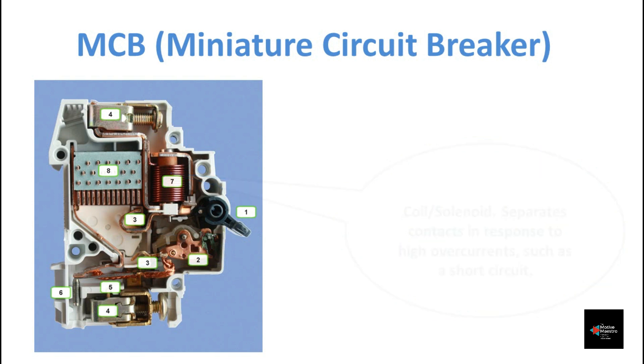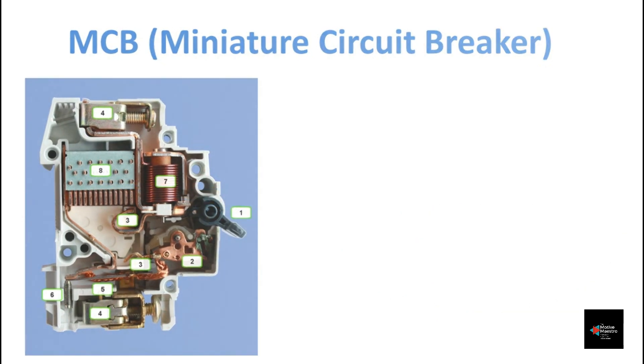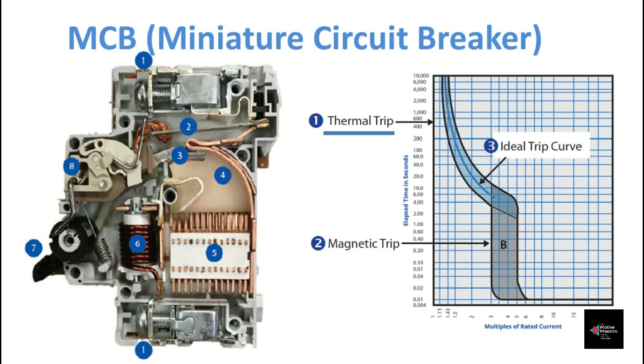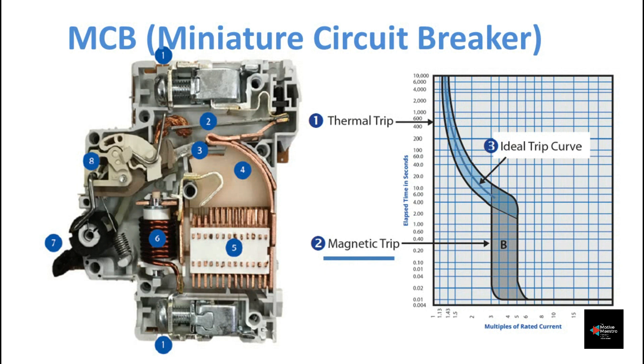The arc divider and extinguisher breaks the main arc into smaller arcs and extinguishes them. During overcurrent, the MCB trips due to the heating and deforming action of the bimetallic strip — so this is called a thermal trip. During short circuit, the MCB trips due to the magnetizing action of the solenoid coil — so this is called a magnetic trip.